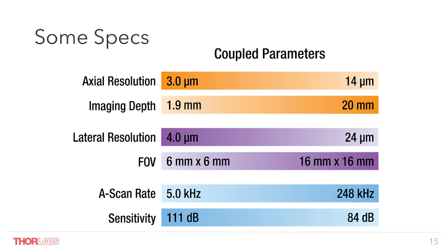The same basically also applies to the lateral dimension. We offer three different scan lens types with different NAs, with which we can achieve different lateral resolutions — but if we want to scan a larger field of view, we have to compromise on resolution. The third intercoupled pair is the A-scan rate and sensitivity. In all our spectral domain OCT systems you can choose from a range of presets to control the readout rate of the spectrometer camera, which controls the number of photons reaching the detector and directly translates into sensitivity. If we want to see faintest features we have to scan more slowly, and if the application requires high-speed readout, we have to compromise on sensitivity.